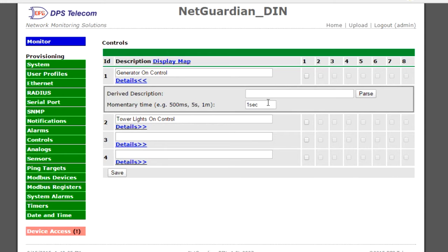So controls, as you asked before, we have that user configurable duration for the momentary. It's a derived description. So depending on the equation that we have, what this is saying is we want to OR display 1.1, and if that's ever set in alarm state, we're going to latch that control. So depending on certain alarm conditions, you can expand that equation and you can control your control states based on incoming alarms.